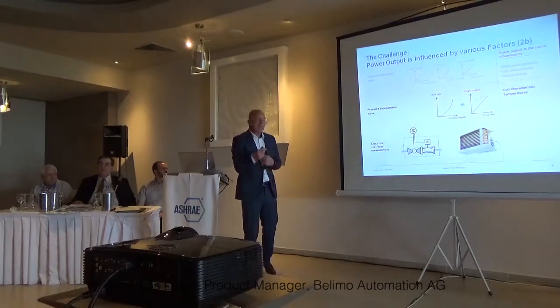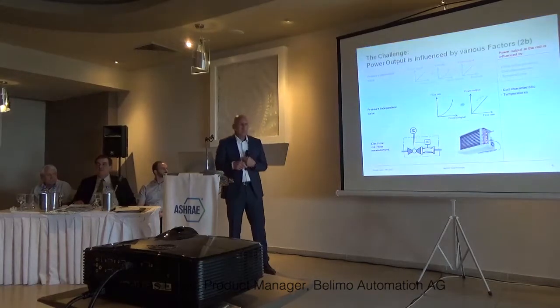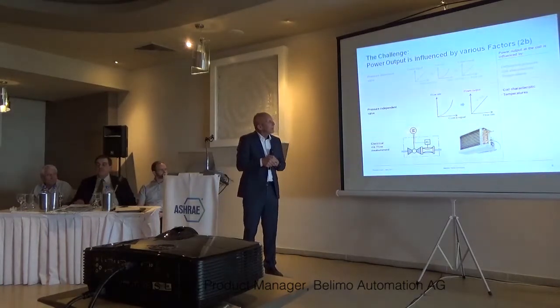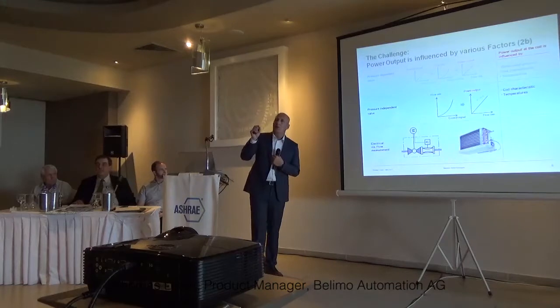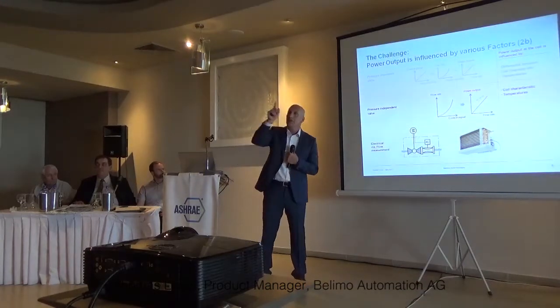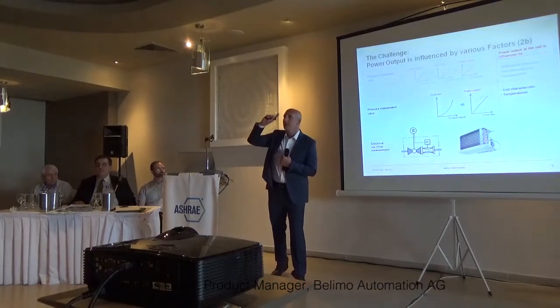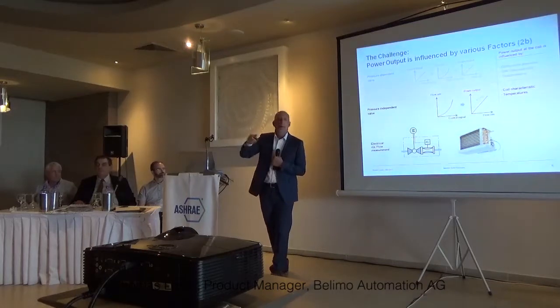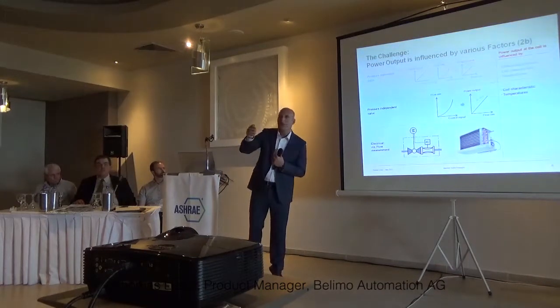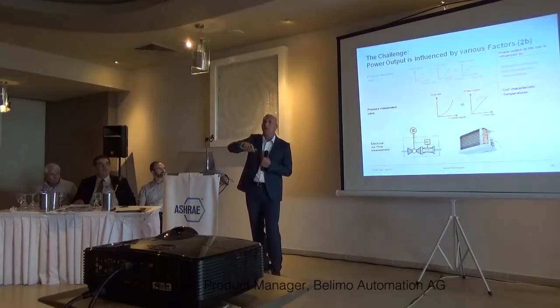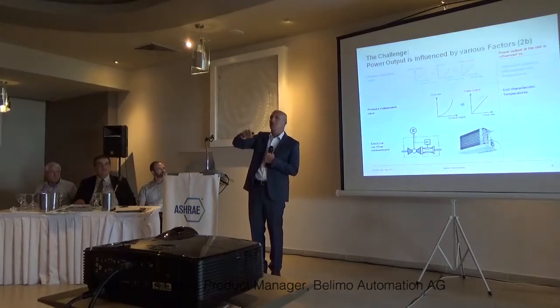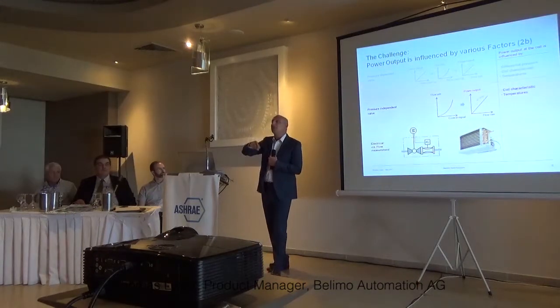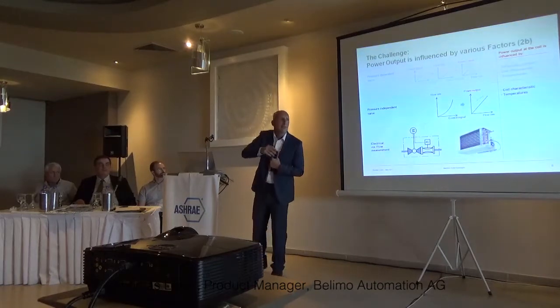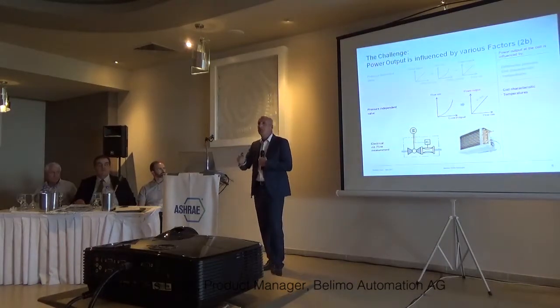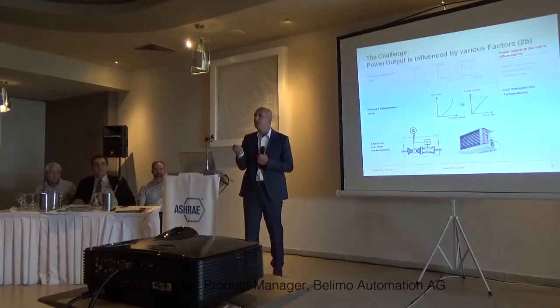These ones, the electric pressure independent valves, will also refer control signal equals flow. With these ones, usually you have also the possibility to change the flow. That means 10 volts should not be just 100 liters. It might also be 93 or 125. You can set this with parameters normally.